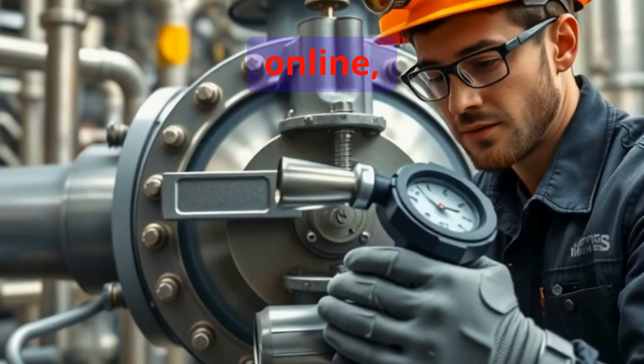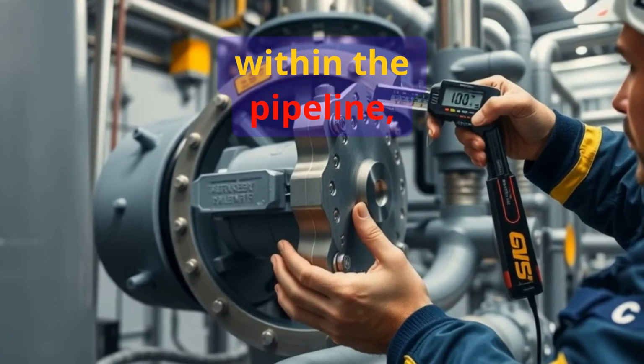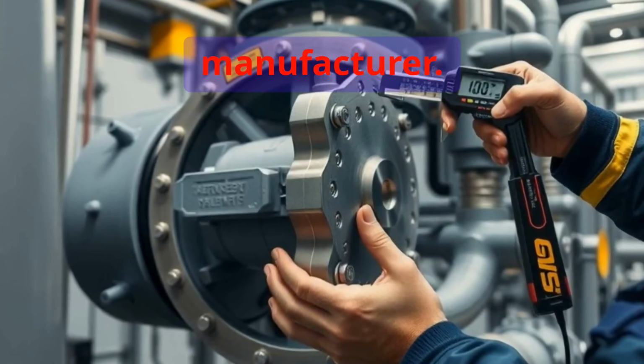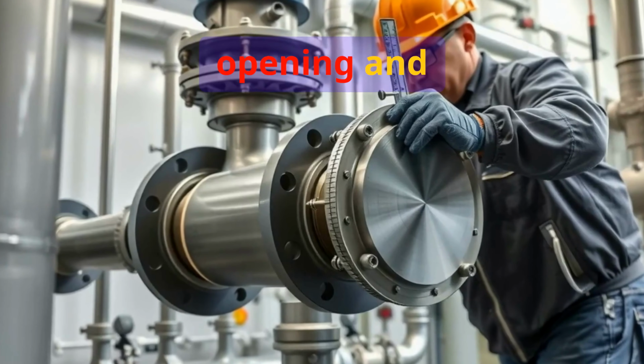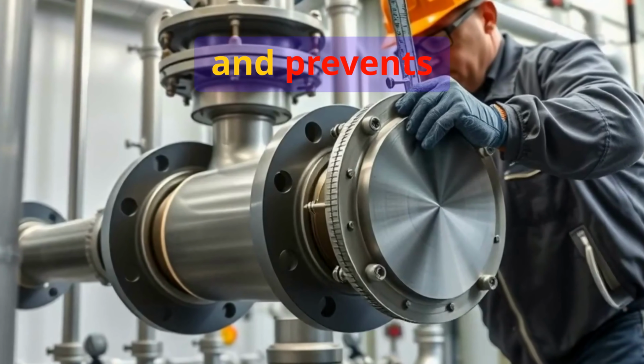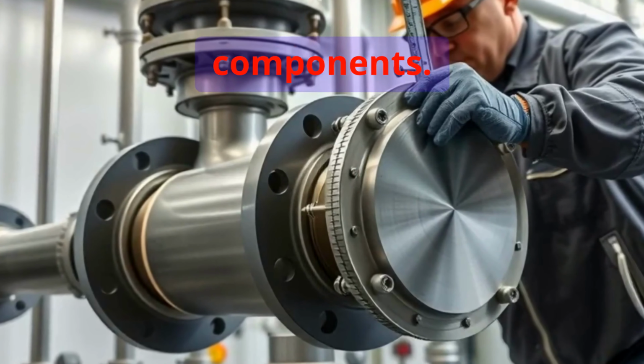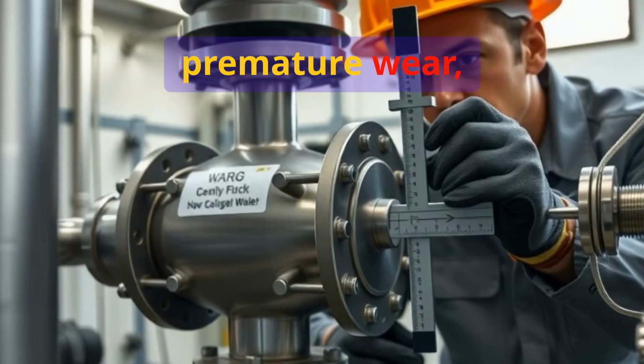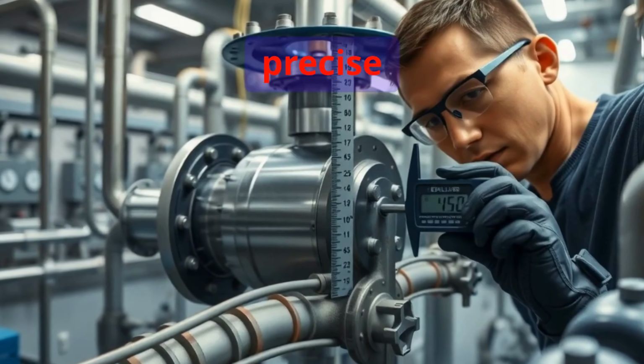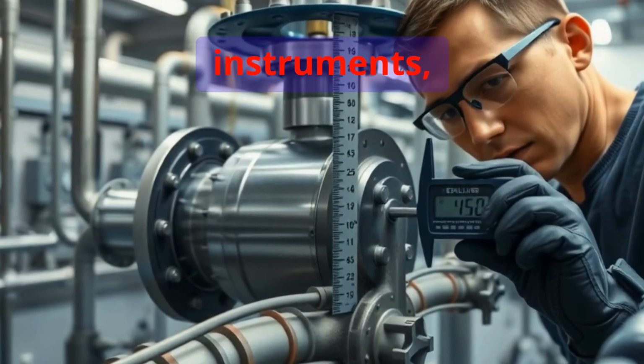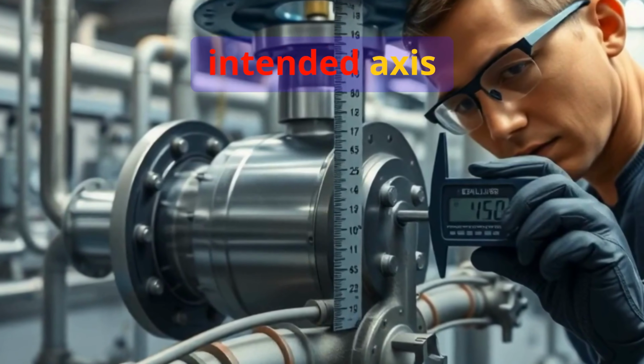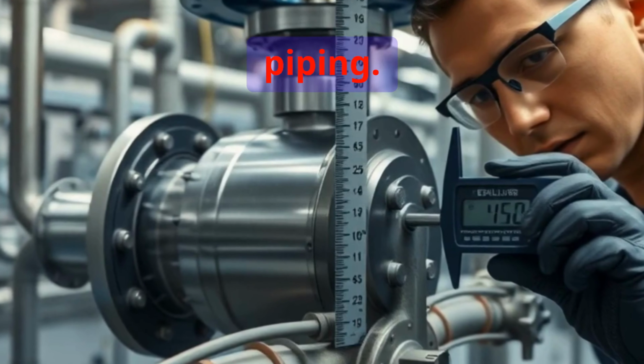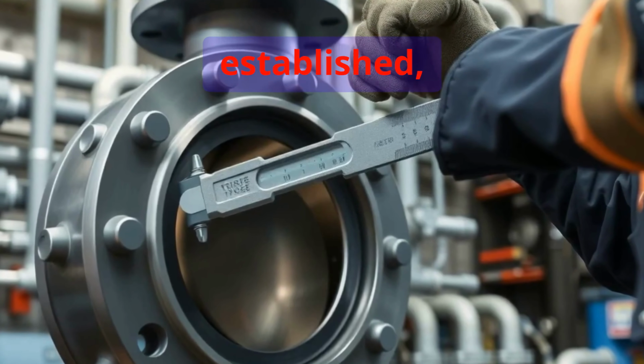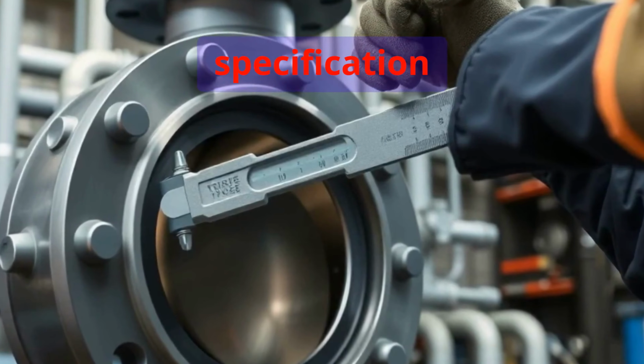Before a valve ever comes online, it must be positioned correctly within the pipeline, following the flow direction as indicated by the manufacturer. This ensures optimal opening and closing, mitigates turbulence, and prevents undue stress on seals and internal components. Misalignment, even by a small margin, may cause premature wear, uneven pressure distribution, or even catastrophic failure. Therefore, precise alignment is checked using calibrated instruments, making sure the valve operates in its intended axis relative to upstream and downstream piping. Once correct orientation and alignment are established, the focus shifts to torque specification adherence.